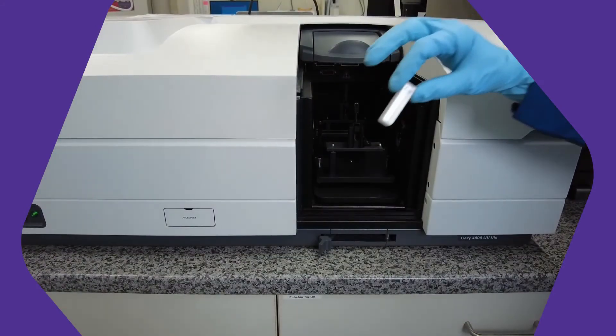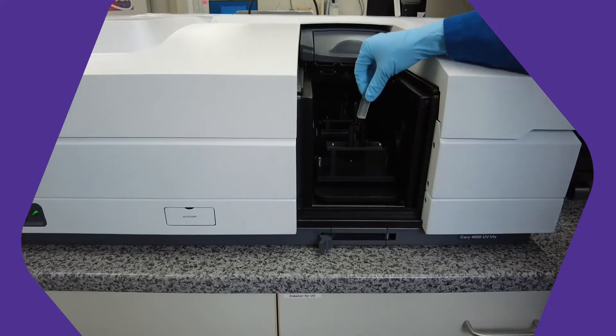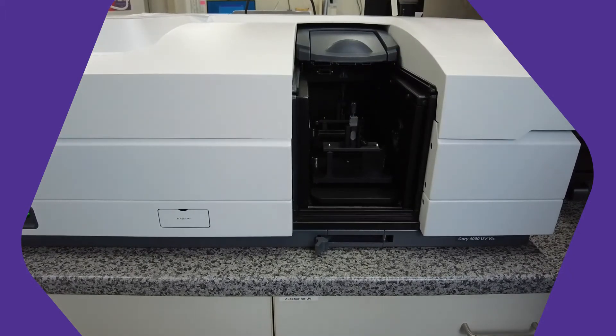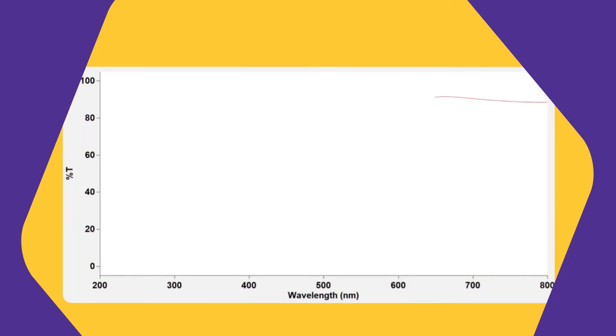We put a clean, empty cuvette into the analyzer and measure our baseline. The light shines from left to right where the value of the light which came through is measured. We can see that all parts of the measured spectrum came through.